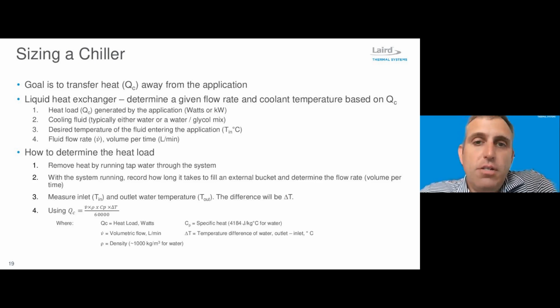So in addition to taking all the heat out of the application and rejecting that into the air, the compressor in the system is also cooled by the refrigerant. And so this heat is being rejected as well. It tends to be about a 30% increase above the total heat load of the application. So in the case of a 3 kilowatt cooling application, you're rejecting a total of 4 kilowatts into the environment. And so we need to, one, make sure that the HVAC system can handle that.